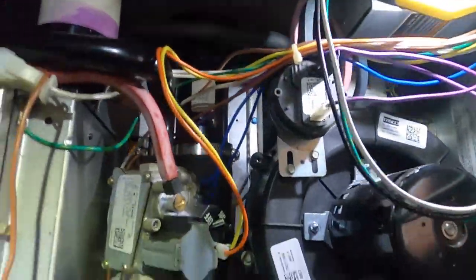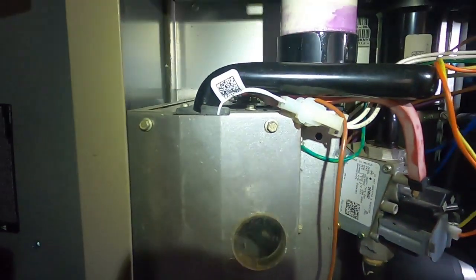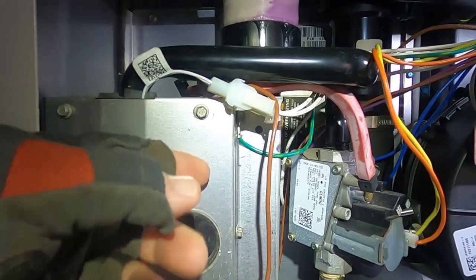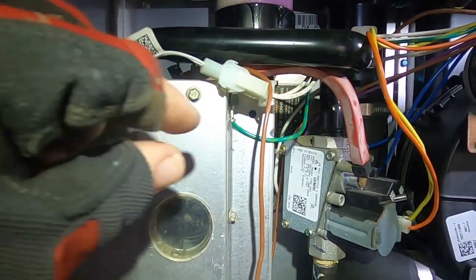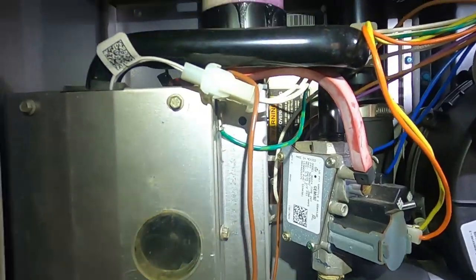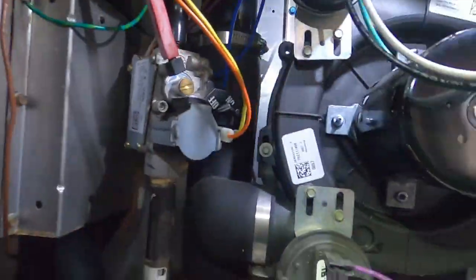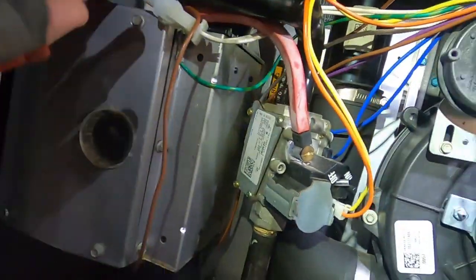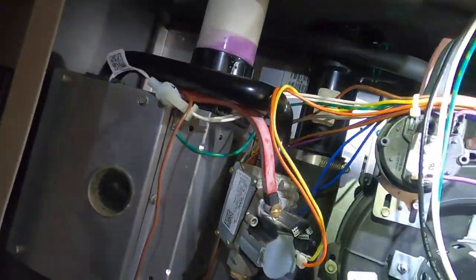So Lennox. We are looking at a 5904, so it's 19 years old, 2004. But typically you're going to see your rust and your corrosion if you've got any of that water dripping and leaking, if that secondary is cracked. But there were some rust spots back in this clamshell type heat exchanger around the back where the seams come. There were a couple of places where we had some pretty good chunks of rust coming through there. And that could just be where it sweats when the air conditioner is running and it condensates in there.